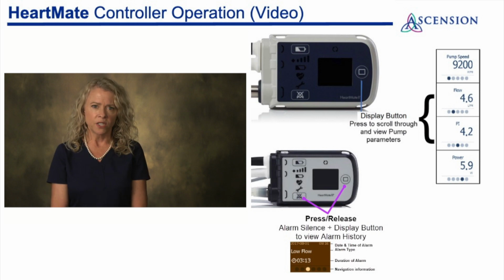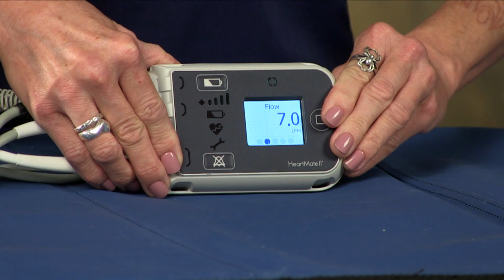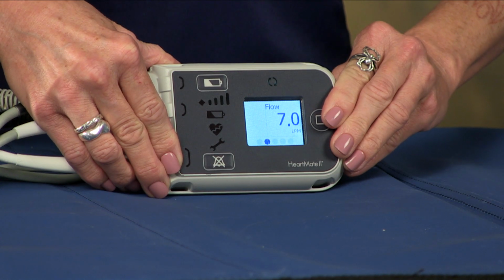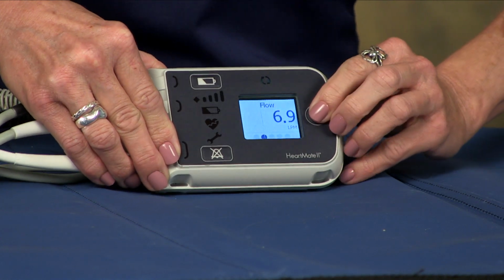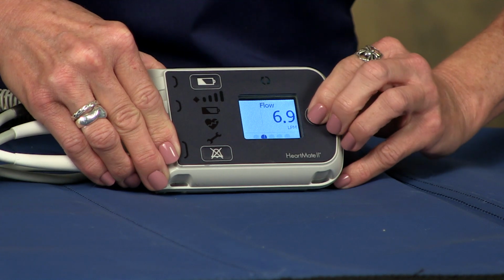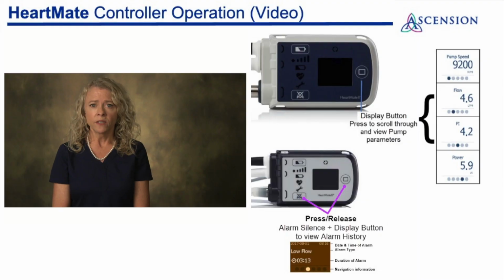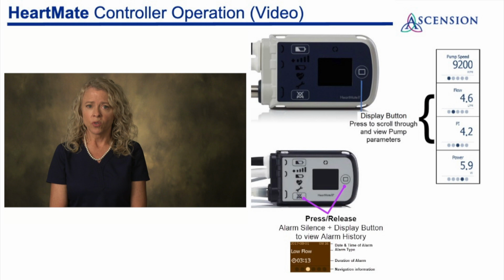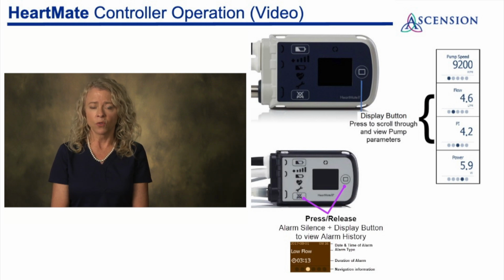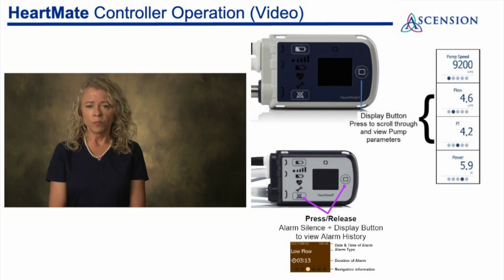Next is the flow that is generated by the motor spinning. It's measured in liters per minute. It's basically an estimated cardiac output based on pump speed, power, and blood viscosity. We like this number to be greater than 3 to be sure the patient is getting blood out for organ perfusion. Then there is PI.